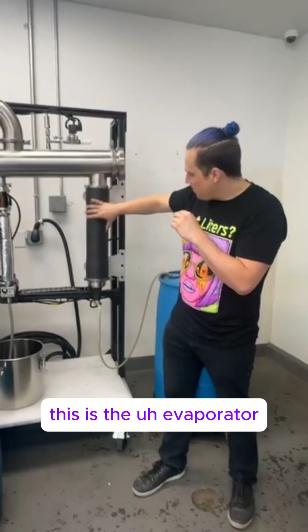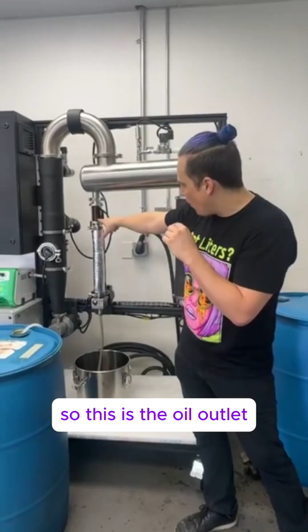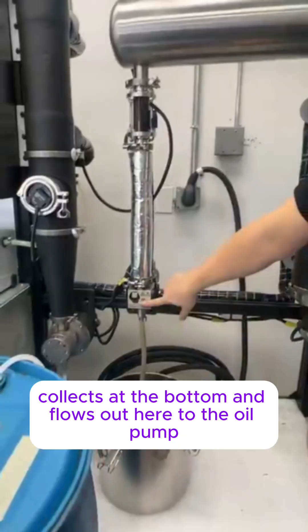This is the evaporator. It's only getting to about 60 Celsius in here, but we're under vacuum, and it's a very high surface area evaporator. So we're actually targeting about 5% residual solvent. So this is the oil outlet. What doesn't evaporate collects at the bottom and flows out here to the oil pump.